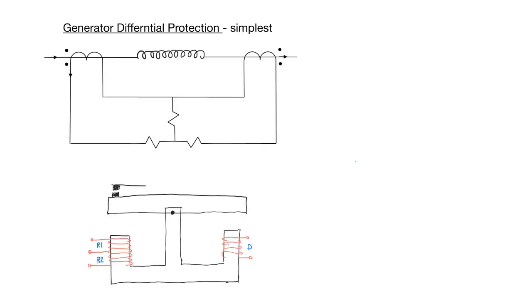Let's now have a look at the operation of a differential protection relay by looking at the simplest form of differential protection, and that is in protecting the windings of a generator. The first differential relays ever built were based off the principles of electromagnetics and electromagnetic circuits. A differential relay has three elements: a difference element and two restraining elements, R1 and R2.